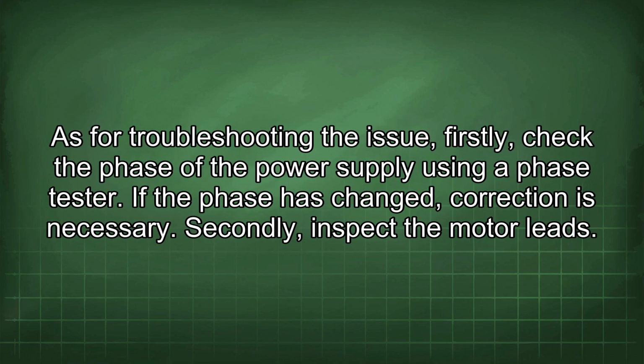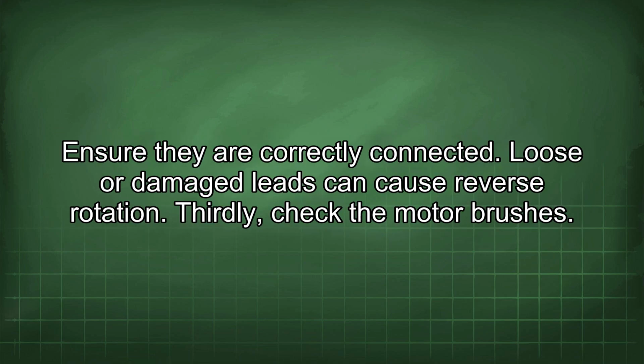As for troubleshooting the issue, firstly check the phase of the power supply using a phase tester. If the phase has changed, correction is necessary. Secondly, inspect the motor leads. Ensure they are correctly connected. Loose or damaged leads can cause reverse rotation.